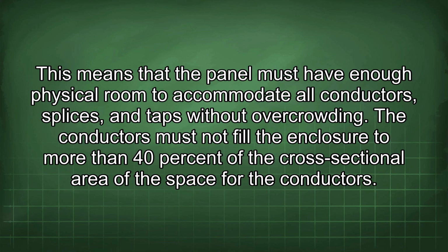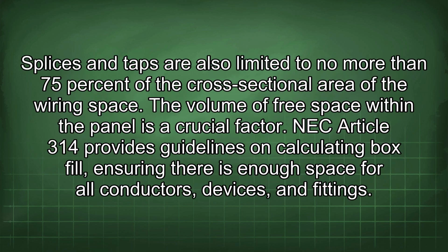The conductors must not fill the enclosure to more than 40% of the cross-sectional area of the space for the conductors. Splices and taps are also limited to no more than 75% of the cross-sectional area of the wiring space. The volume of free space within the panel is a crucial factor. NEC Article 314 provides guidelines on calculating box fill, ensuring there is enough space for all conductors, devices, and fittings.